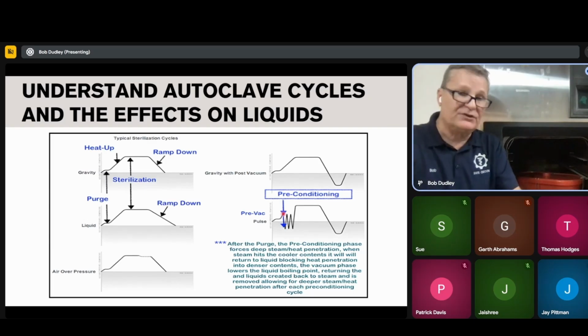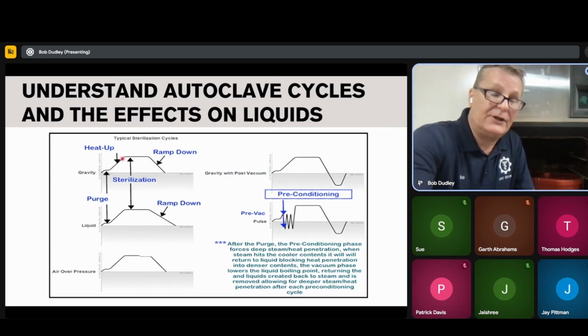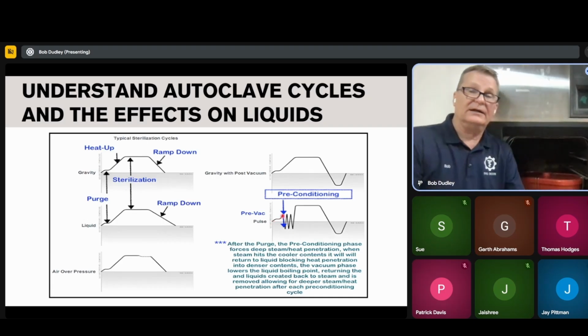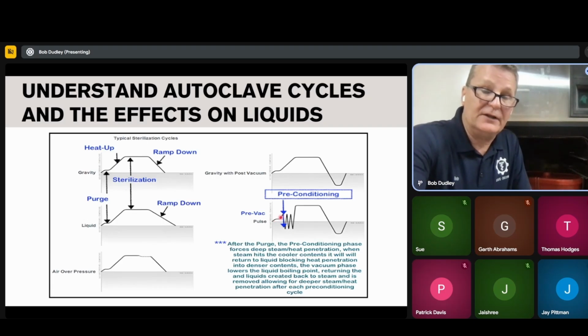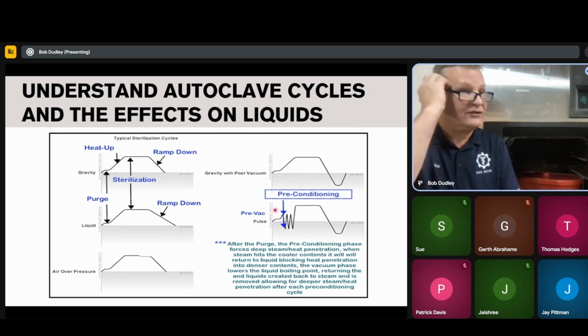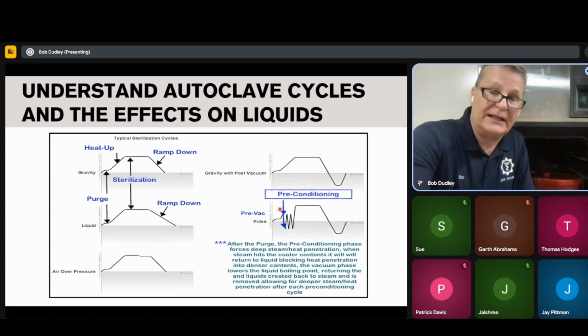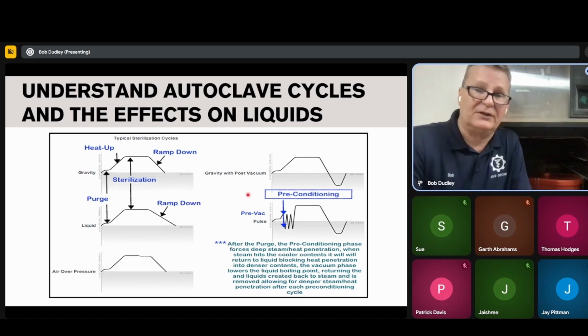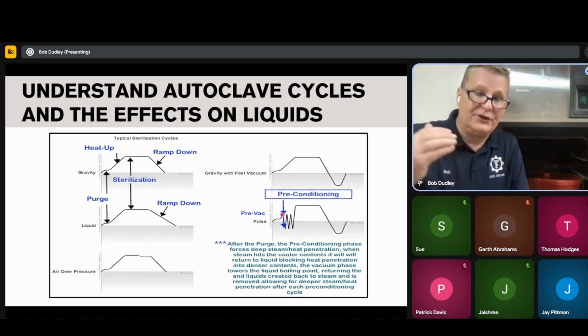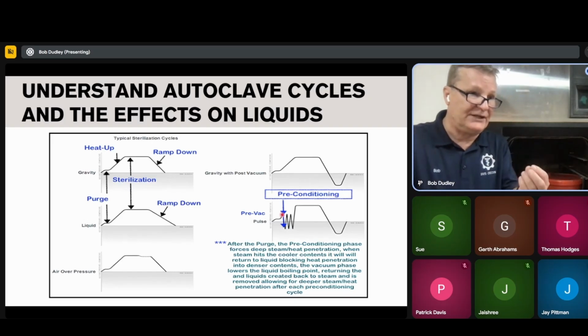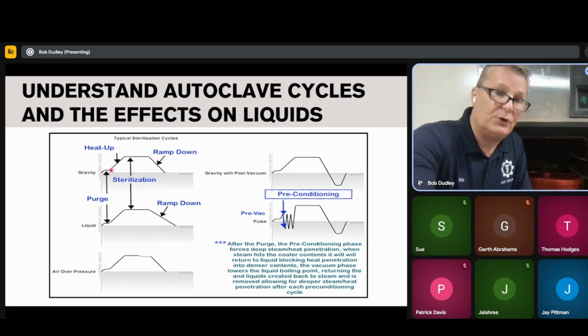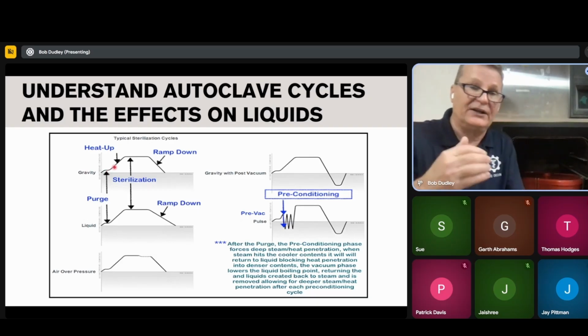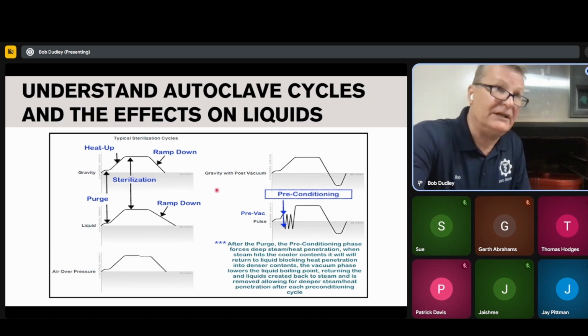Now, what happens generally with steam, and this is why you're going to get a lot of failures with the gravity and the liquid that you're not going to get necessarily with the pre-vac, is you're going to push in steam pressure. As a rule, it'll push in about 9 to 10 psi. But what generally happens is when you're trying to get penetration on something, and I'll show you here on my test packs and explain a little bit better, but when you push that in and you start driving that steam into hard to get places, steam has a tendency to turn into water. So with this, you're pushing it in, the steam has to push in, and as it gets into the tighter, cooler places, it's gonna turn into that mist, and then it's going to block it. Liquids are an insulator to heat.